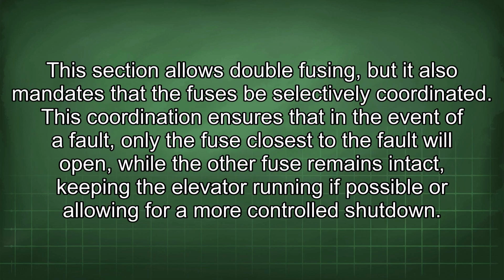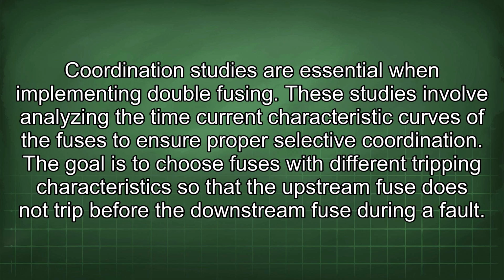620.22b2. This section allows double fusing, but it also mandates that the fuses be selectively coordinated. This coordination ensures that in the event of a fault, only the fuse closest to the fault will open, while the other fuse remains intact, keeping the elevator running if possible or allowing for a more controlled shutdown. Coordination studies are essential when implementing double fusing. These studies involve analyzing the time current characteristic curves of the fuses to ensure proper selective coordination. The goal is to choose fuses with different tripping characteristics so that the upstream fuse does not trip before the downstream fuse during a fault.